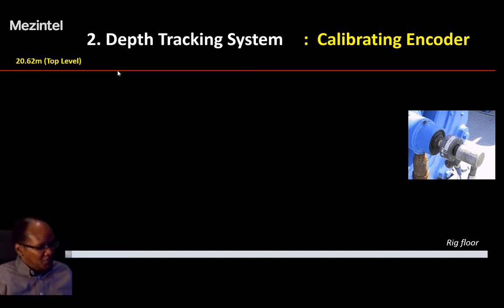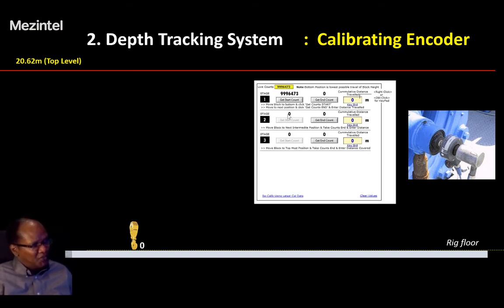So the first step you do is to move the block to the bottommost position, and you're going to call that position number 0. Once you get to that position, you go to the software. There's going to be a wizard that you can use, and you're going to call counts for that particular position number 0, in which case right now by pressing the get start count, it will populate the counts for the position number 0 as the one that's ending here with 473. And in this case, I have chosen a 3-stage calibration. So you can see the stages are numbered right there, 1, 2, 3. And right now we're on the first stage at the very bottom position.